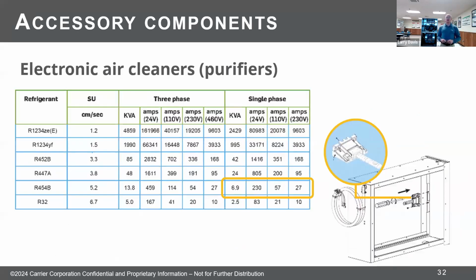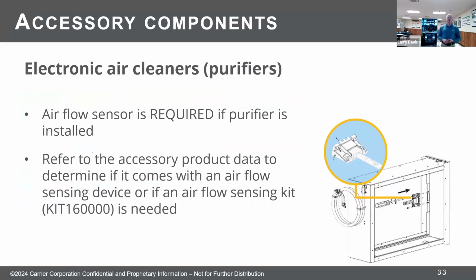Oh, here's the chart. It's well ahead of where I thought it was. So this chart exists: for any particular refrigerant, this is what the single phase amp rating or amp draw would be at any given voltage. Anything above that is considered an ignition source. As you can see, we're nowhere near that on any of our products. However, it is required because it can produce a spark in an air purifier. It's required that you have that airflow sensor in it. A lot of the new ones will come with it. If it does not, then there's a kit number that you'll have to add.